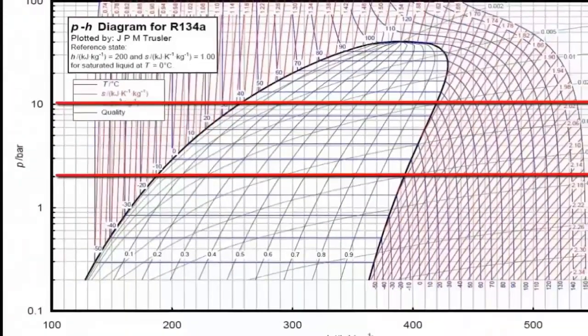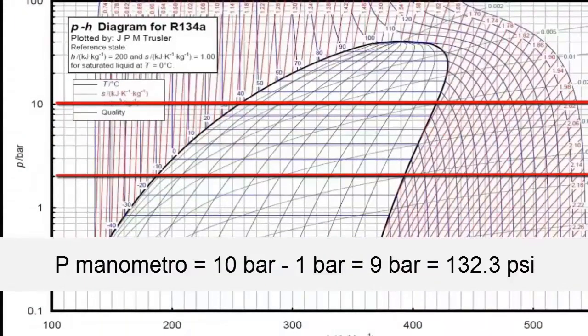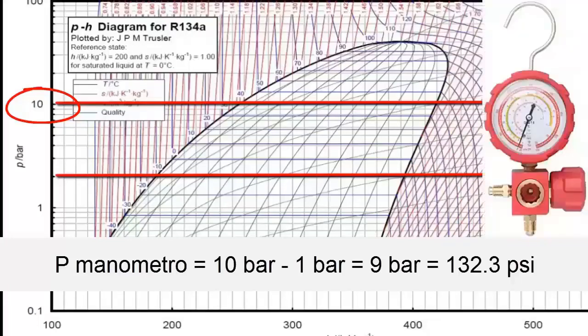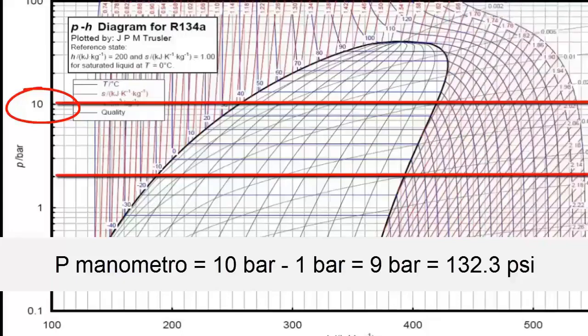In the Mollier diagram, for this temperature value there is an absolute pressure of 10 bars. To find the pressure that the manometer should read, we must subtract the atmospheric pressure from the absolute pressure. By subtracting 10 bars minus 1 bar from the atmospheric pressure, we have a manometer pressure of 9 bars. Then the high or red pressure gauge should read 9 bars or 132.3 psi.